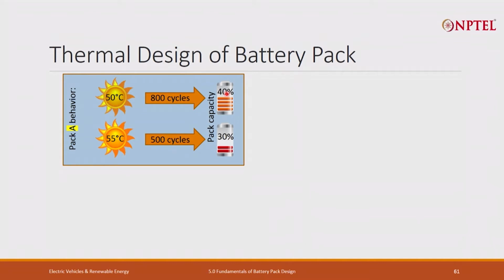So there are two things that happen. Not only has the cycle life come down, now cycle life has come down to 500 cycles, but at the same time my pack capacity has gone down to 30%. So if I have to compare apple to apple, this cycle may be further down, maybe 300 cycles, maybe 250 cycles. If the pack capacity is at 40%, in that case my cycle life may be 250 cycles.